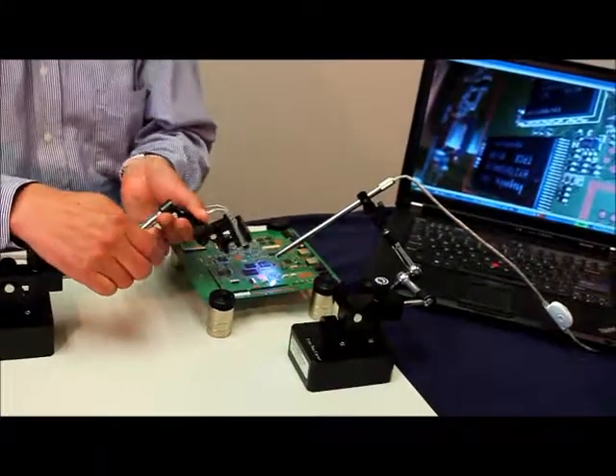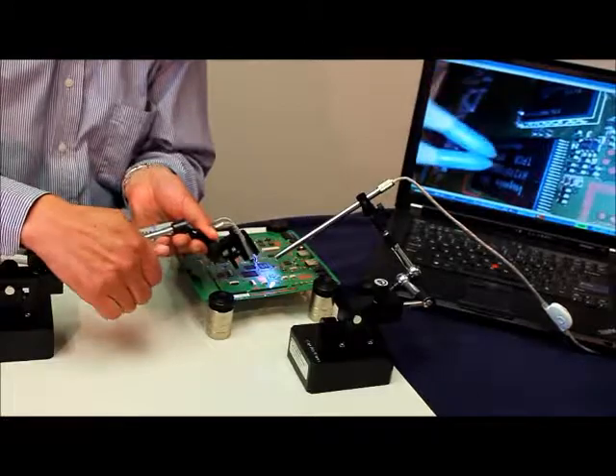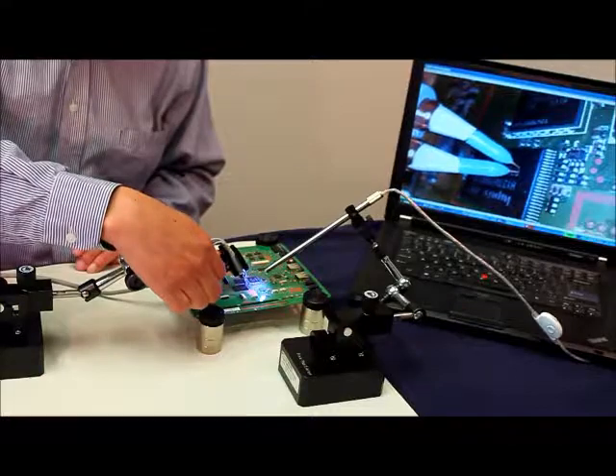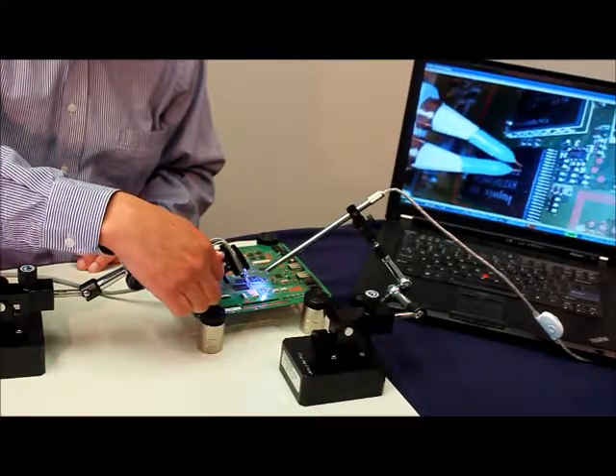Loosen the big knob to orient the probe tips closer to the probing position. Adjust the theta knob close to the tip of the probe holder such that the signal ground pins are on the same plane.